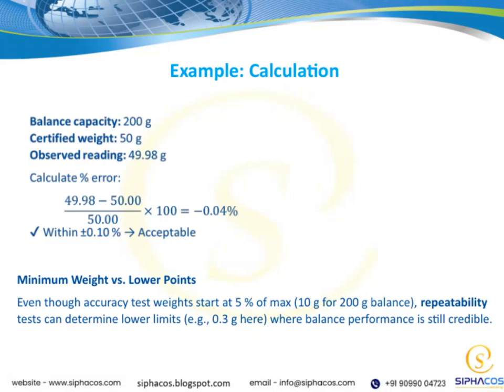Let's talk about minimum weight versus lower points. Even though when we start accuracy testing, weights are typically set at about 5% of the maximum capacity, so for a 200-gram balance, that's around 10 grams. We can actually go lower if the balance still performs reliably. Repeatability tests help us identify those lower limits, like the 0.3 grams shown here, where the balance's performance remains credible.